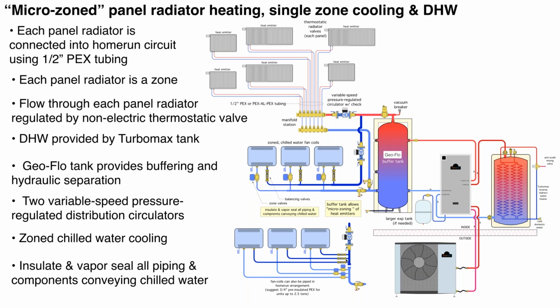The other way you could do it would be more of a home run arrangement, where you keep the zone valves as well as the balancing valves. You keep all that in the mechanical room, and then you go out with insulated piping to these console fan coils. Last week, I believe I mentioned you can buy pre-insulated PEX tubing. We've used 3/4 inch pre-insulated PEX tubing. I like it because you don't end up having to slide the insulation on it, glue it, and so forth. You basically uncoil it, pull it through the building, and you've got an insulated and vapor tight piping system for chilled water.